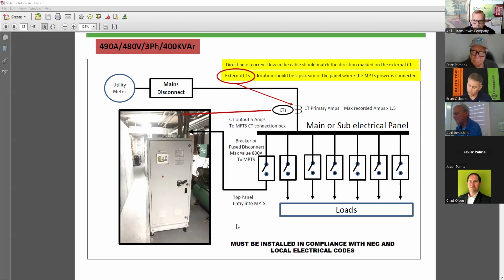And then going over those problems with the installation of that Accu Energy integrator, that was really good, especially pointing out that you've got to be very careful about the phase configuration coming into the integrator and out of the integrator, as well as the polarity of your CTs. Correct. Making sure the installer understands how the CTs work and what proper installation is.